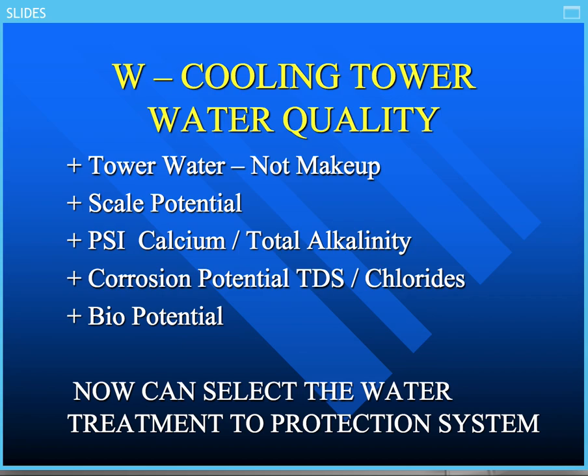The other one, of course, is the corrosion potential. What are the TDS and what are the chlorides? Those are the two most important areas that we look at, particularly the chlorides if you have, of course, stainless steel. Then we have the biopotential. To me, biological control is absolutely one of the most key areas in any type of treatment program, particularly a first-rate cooling water treatment program. You need to have good biological control, which will reduce corrosion problems. It'll reduce some scaling problems. So consequently, it will improve operation of the equipment.